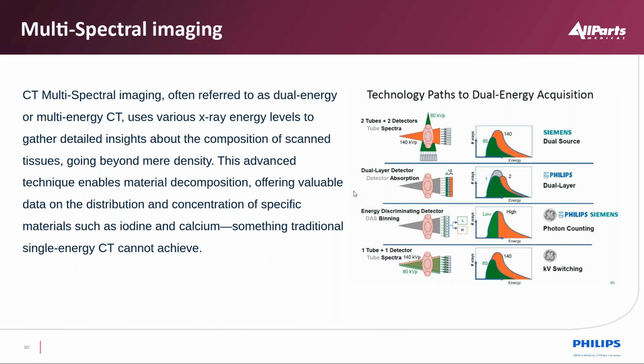Another aspect of newer technologies is multispectral imaging. If you think about it, if you have one tube shooting 80 kV and another X-ray tube shooting 140, what would that mean? Well, 80 kV, or lower kV energies, would get absorbed more by soft tissue than bone and those kinds of things, whereas 140 will penetrate through them, be less attenuated. So with those two spreads you can see in the energy spectrums, that allows us to look at soft tissue and enhance what we see with iodine and calcium as well.